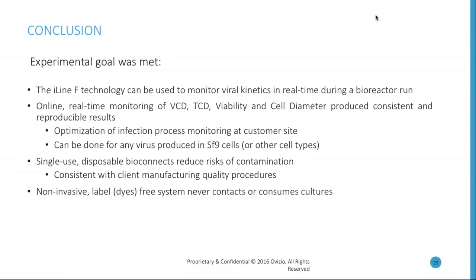There is online real-time monitoring of viable cell density, total cell density, viability, and cell diameter, producing consistent and reproducible results. An optimization was done for the infection process monitoring at the customer site, but we can do this basically for any virus produced in SF9 cells and even in other cell types.